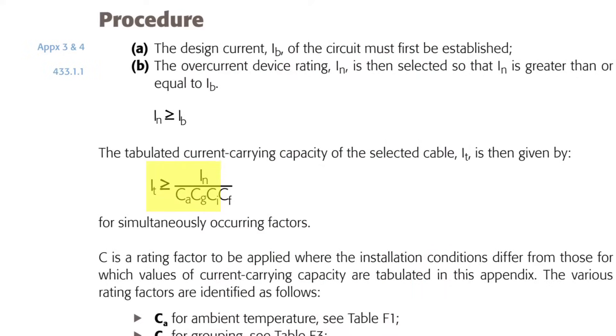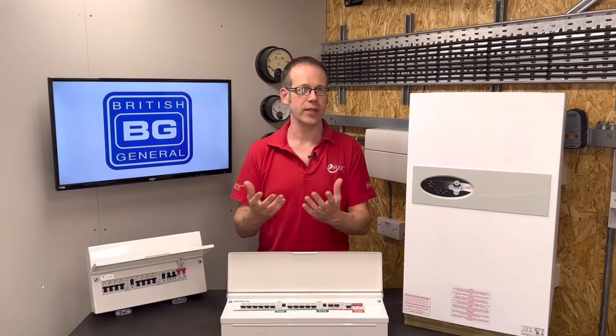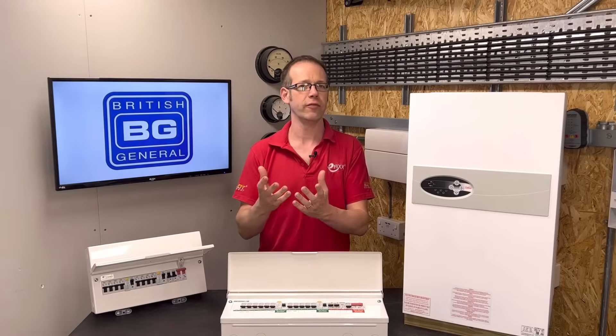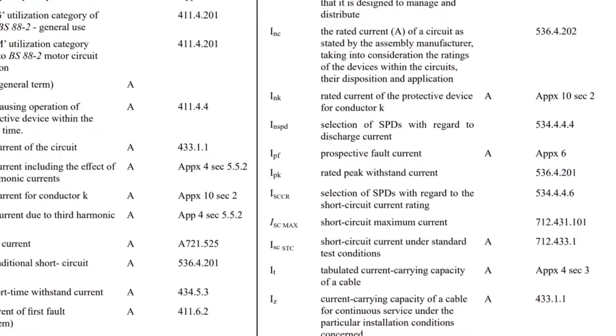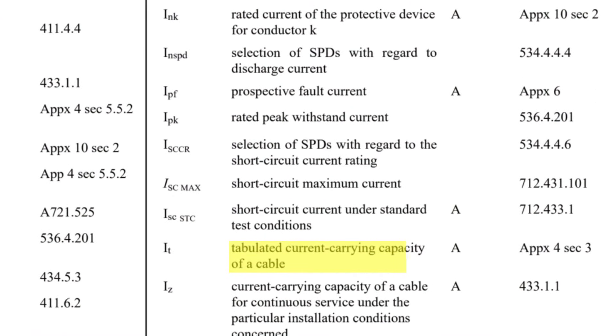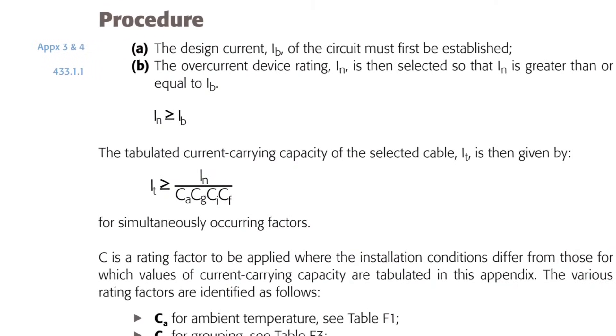In appendix F of the guide we find this formula: IT must be greater than or equal to IN divided by CA times CG times CI times CF. It looks a little daunting to start with but it's pretty straightforward when we break it down. IT — I with a lowercase t subscript — means the tabulated current carrying capacity of a cable, meaning its value is recorded in a table. IN is the nominal rating of the protective device, and all those C's along the bottom of the formula are our rating factors.